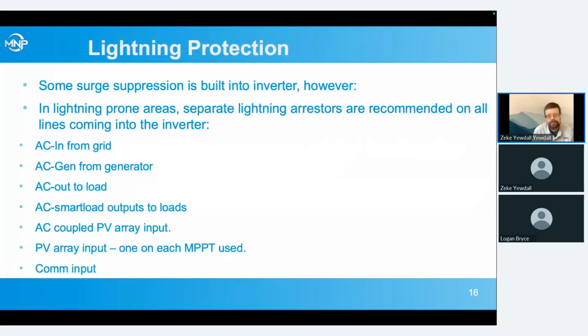Lightning protection. We do have some surge suppression built into the inverter, so it's better protected than a lot of the inverters out there. However, we still recommend in lightning prone areas, separate lightning arresters on anything coming into the inverter. AC in, AC generator, unless the generator is physically sitting like 5 feet away from the inverter in the same equipment building. AC output to loads, lightning strikes on the house getting into the AC wiring and coming back into the inverter through the loads is a common point of entry into the inverter.